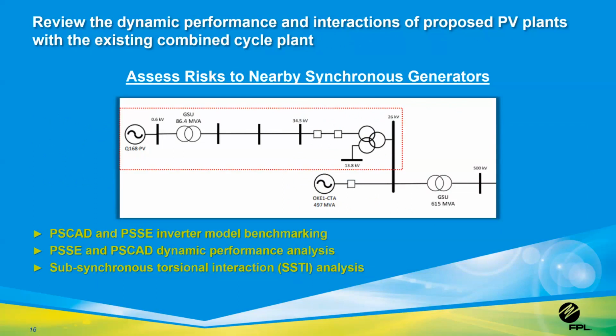So we had a proposal to interconnect a PV plant to the low side of a GSU at an existing combined cycle plant. The interconnection study for this new PV plant demonstrated that there were no load flow, no short circuit, or no transient stability concerns. The weighted short circuit ratio was well above 5, since it's right next to a large conventional plant. But we had never done this before.